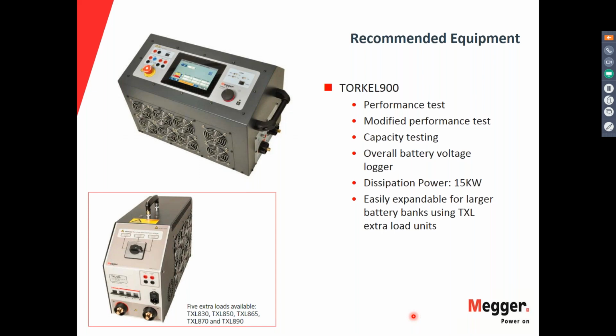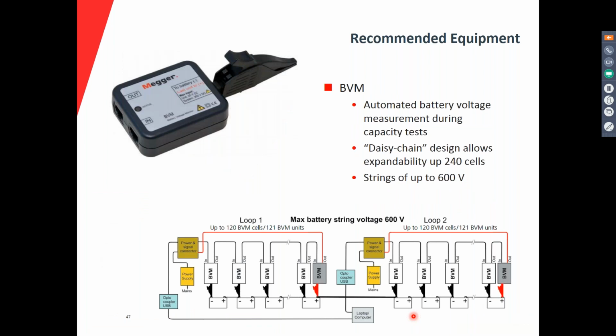The maximum dissipation power of the unit is 15 kilowatts. And if you need more dissipation, you can expand the system by adding extra loads, which are called the TXLs. Then for individual voltage monitoring, we have the BVMs, which are a string of little boxes that you connect on each cell, and they will automate the battery voltage measurement. They are connected daisy chained. You can measure up to 240 cells, and strings of up to 600 volts.